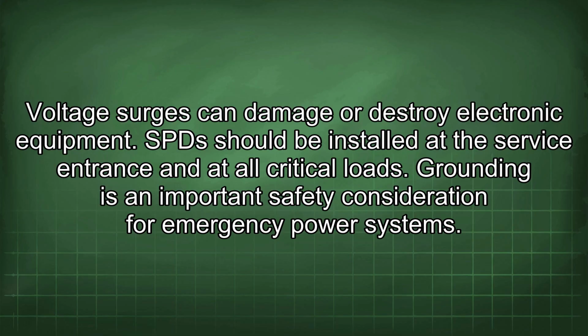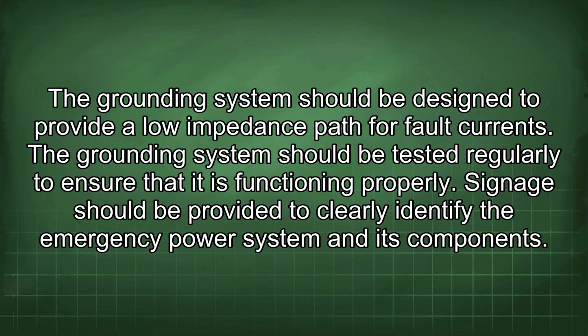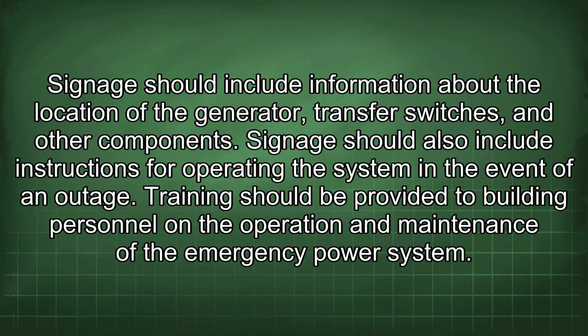Grounding is an important safety consideration for emergency power systems. The grounding system should be designed to provide a low impedance path for fault currents. The grounding system should be tested regularly to ensure that it is functioning properly. Signage should be provided to clearly identify the emergency power system and its components. Signage should include information about the location of the generator, transfer switches, and other components. Signage should also include instructions for operating the system in the event of an outage.